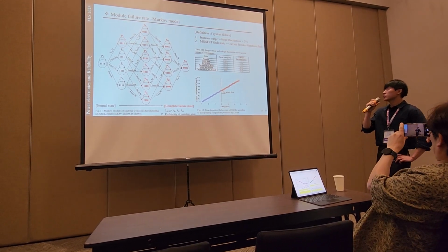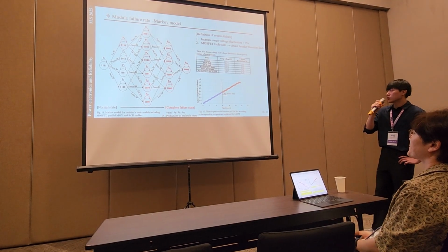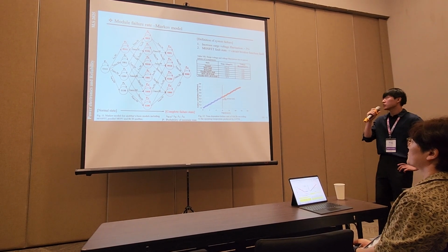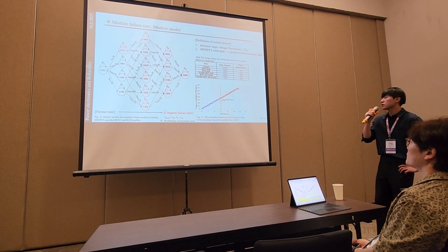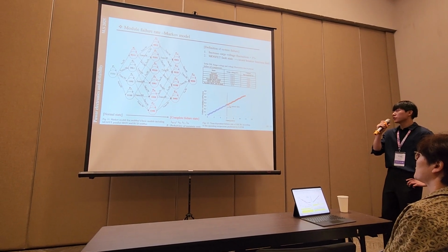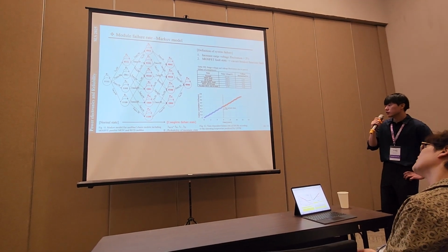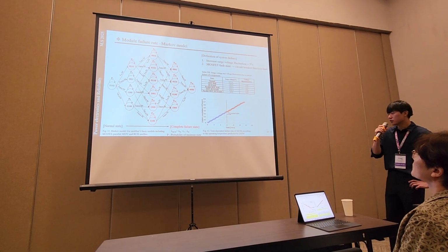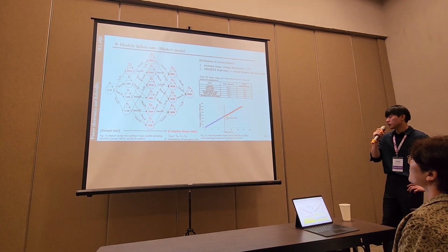The first definition of system failure is that the surge voltage reduction decreases by more than 3%. According to table 7, when more than 2 components fault, the surge voltage reduction decreases by more than 3%. And the last definition of the system failure is the MOSFET failure state, because when the MOSFET faults, the circuit breaker function faults. And we calculate the module failure rate as the sum of each probability of system normal state. Figure 12 shows the time-dependent failure rate of the entire snubber circuit.